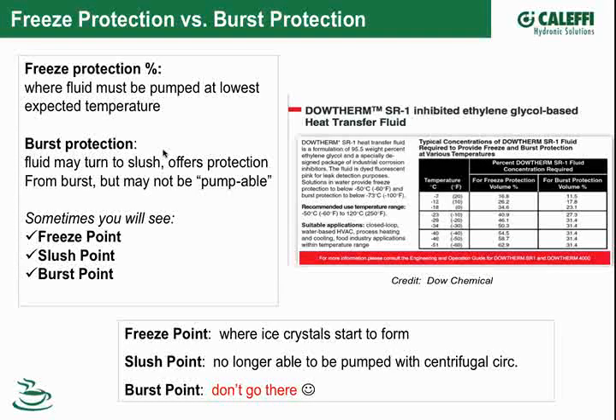The freeze protection point is where an ice crystal will start to form, but you can still pump it. Then there's a slush point, which becomes like a snow cone—it won't burst the pipe, but a centrifugal pump can no longer move the fluid through the system, so you can't move heat to the building or chilled water, whatever it might be, once you reach that point.